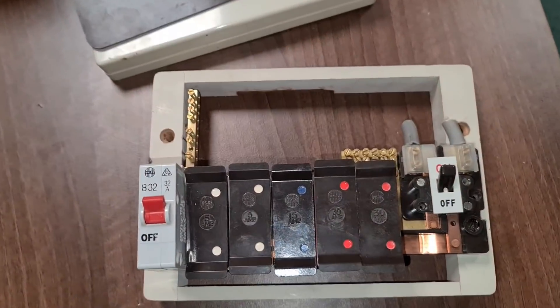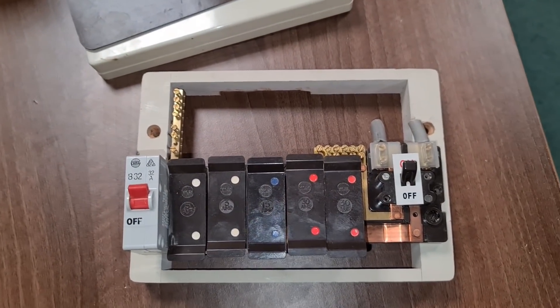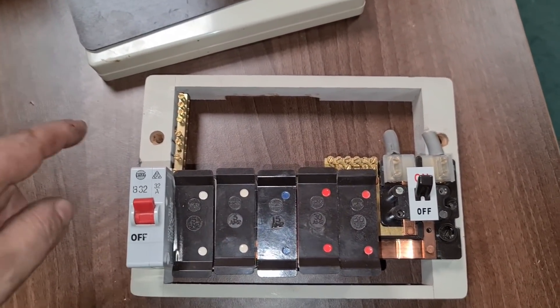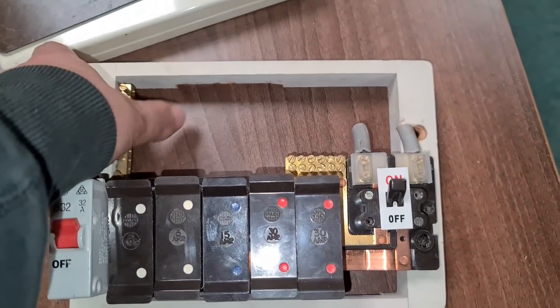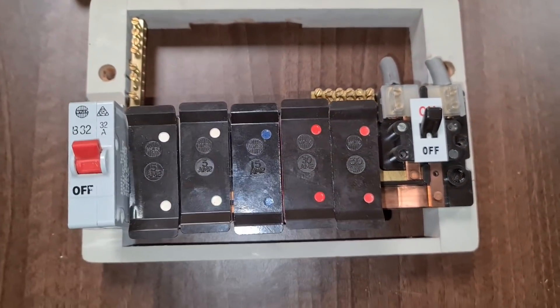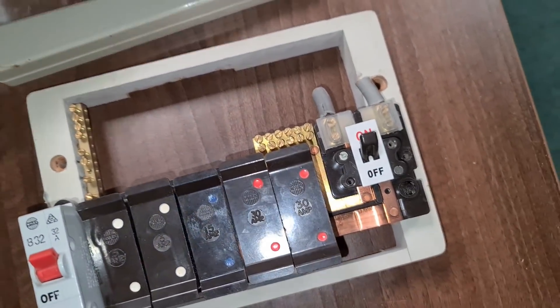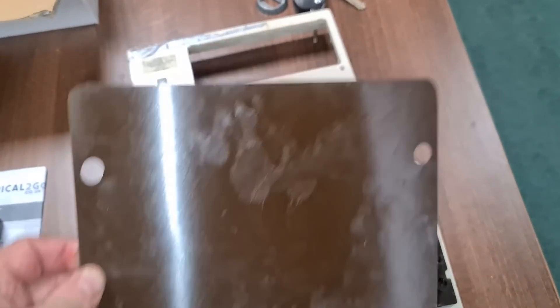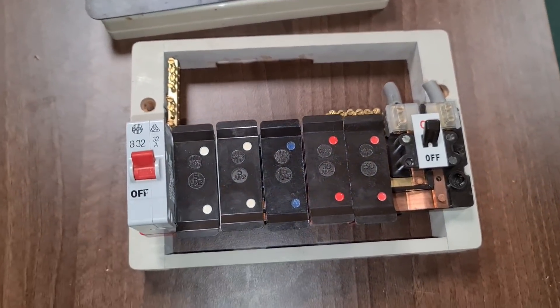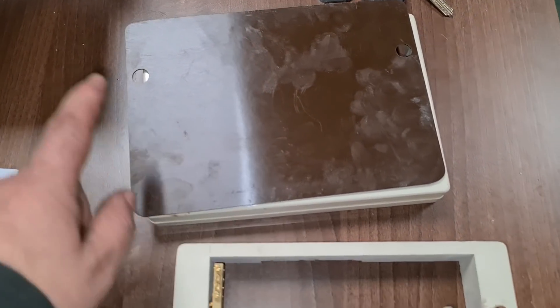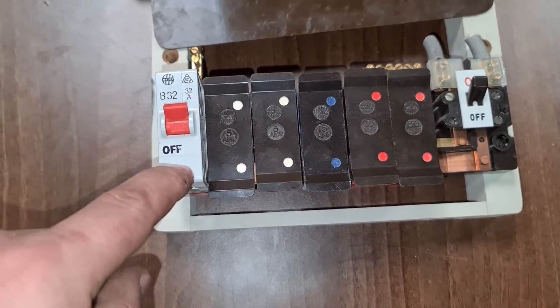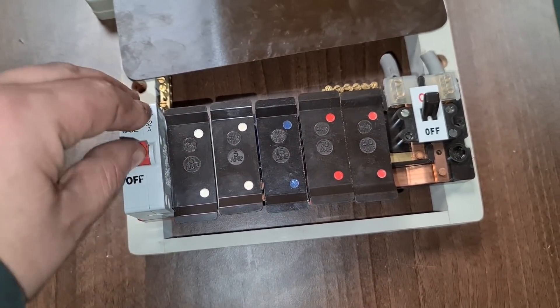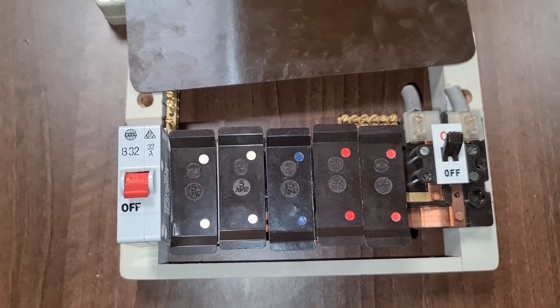So I spoke about these on the consumer unit podcast I did with Rick and Neil. These are quite common, we take loads of these out all the time. So they used to be made of timber and then your fuse wires. This one did have the Bakelite board on the back, so that goes on the wall and sits between the wooden enclosure and the wall surface. These are sometimes missing but this one had it on which was nice. And then again someone's gone on, this was doing a shower which is a little bit naughty really. You know I would have preferred to see RCD protection, it was a newish install.